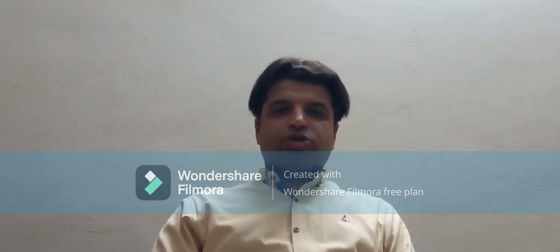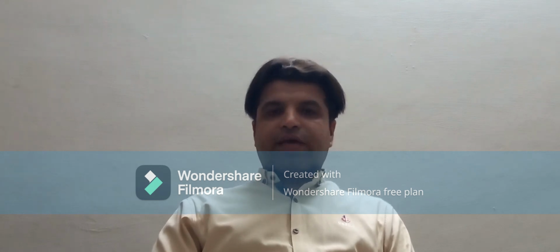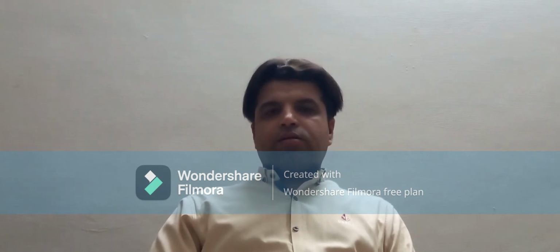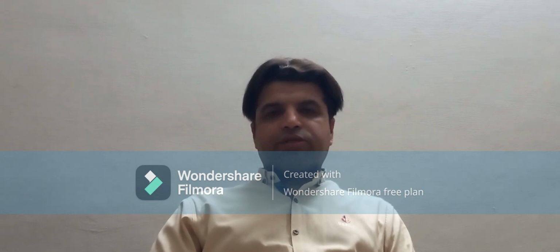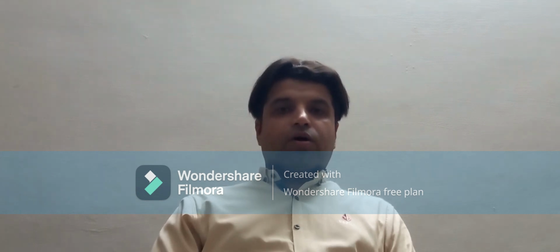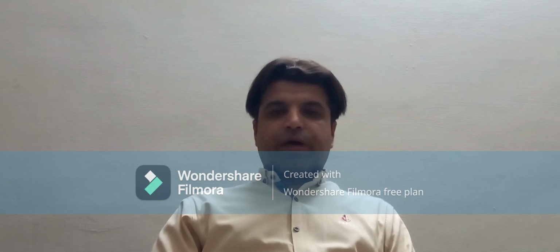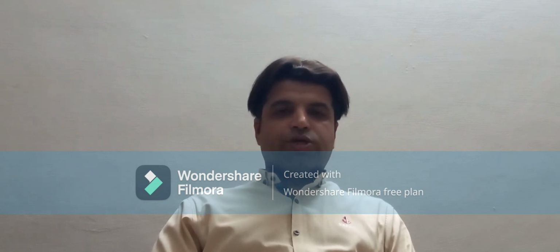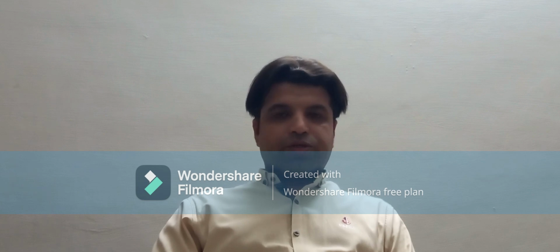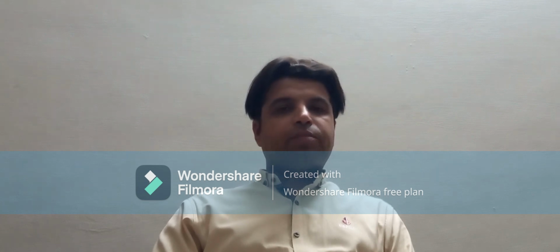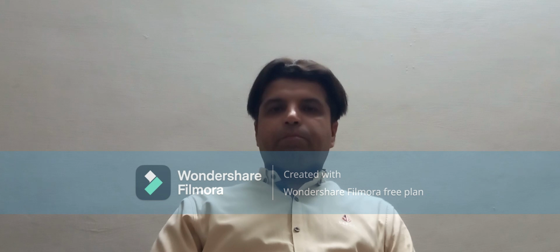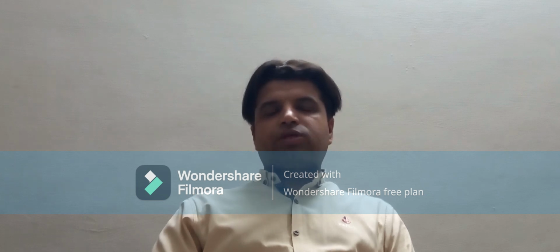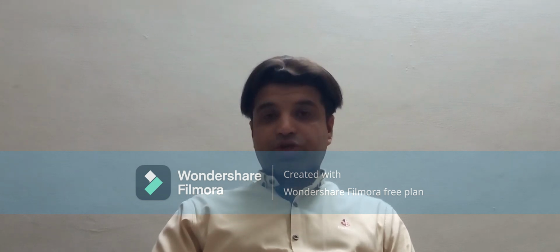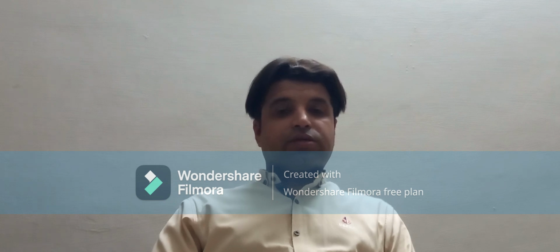Now it takes very short to complete this one scan, so you can scan the molecule multiple times in very short amount of time on the new Fourier transform NMR spectrophotometer. That is the advantage of the new NMR instruments. And what happens when you scan the molecule multiple times is that you are actually increasing the signal to noise ratio, and you are enhancing the signal quality.